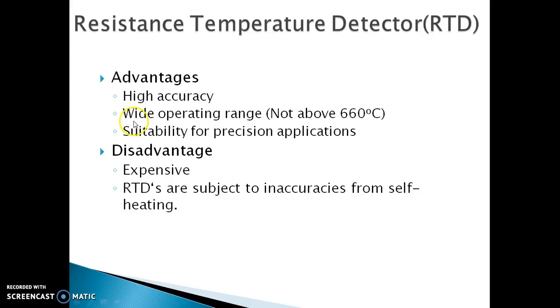The second being the wide operating range. The operating range for the standard RTD is from minus 200 degrees to 660 degrees Celsius. The 660 degrees Celsius is using the platinum RTD.